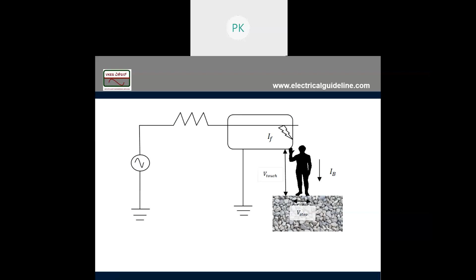How do we find out in a substation connected to a distribution network, when we have many incoming lines? How do we model it? When you have many incoming lines, each line connected to the substation will contribute fault current. Suppose you have 10 lines, each line will contribute fault current according to its own value. So you have to do the detailed fault current calculation. Maybe you can do hand calculation, or if it is very big, you have to use ETAP or some other software.